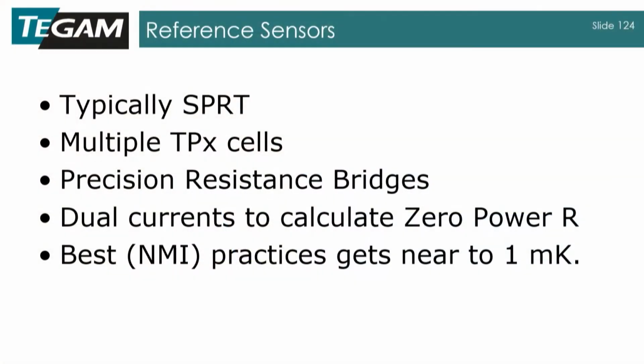I talked about that thermoelectric effect. They'll use bipolar excitation. But another thing, when you get to this level, you're going to use dual currents. So you'll measure a temperature and pass a certain current through the SPRT, then lower or raise it by a known amount. That allows you to plot the zero power point, because when you're passing current through it, you're heating the RTD to some amount. So to subtract that out, if you do it at two different current levels, you can plot on a curve where zero would actually be if you weren't messing with your sensor by passing current through it.